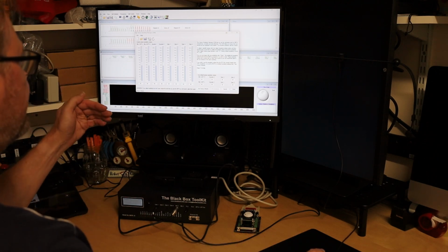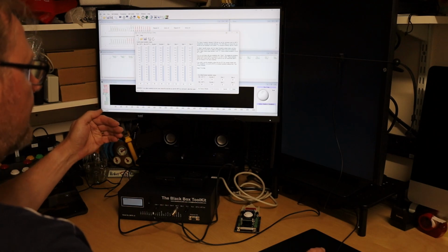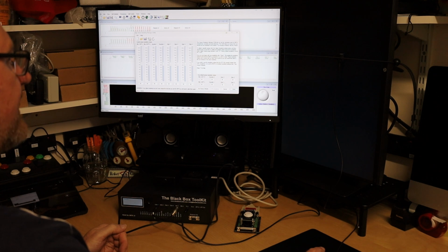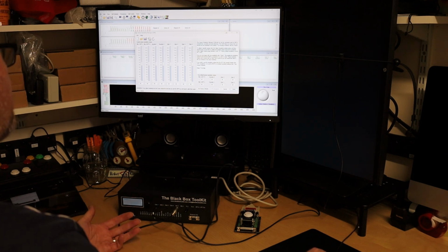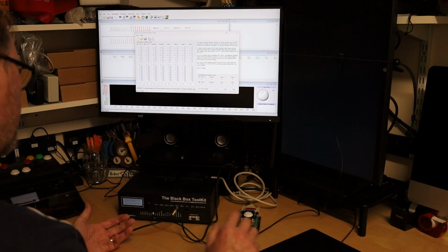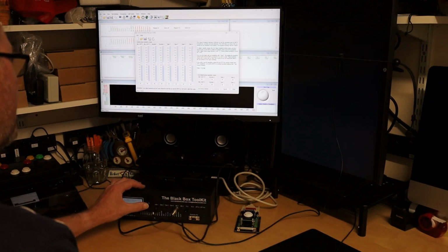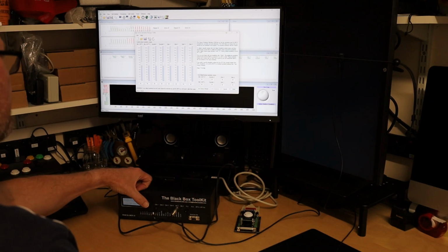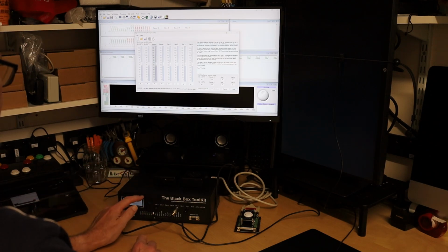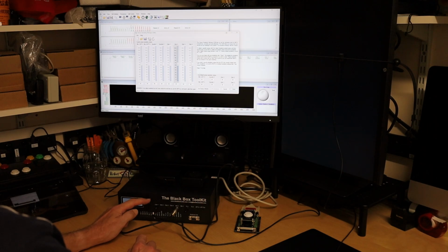The sensors can be auto adjusted, so with the optos you can put a white patch up and it'll auto adjust to the best setting for that, or you can use this sensitivity management tool, so we can basically go through and alter the thresholds, or the sensitivity in other words. So what we can do is I'll just alter the opto slightly, so it's linked, so hopefully you can see me moving the dial, and it moves on screen.